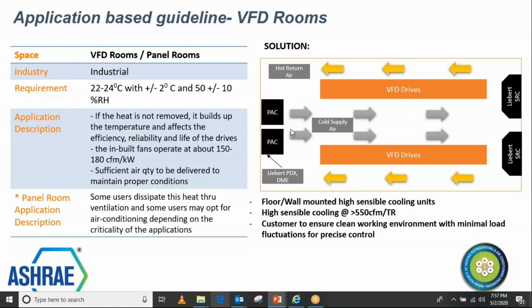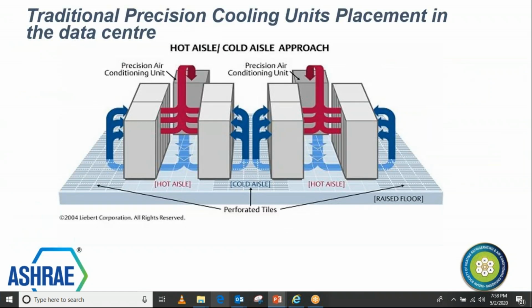This is just assumed here: the front discharge of the cold supply to the VFD drives, and the return coming from the side or from the top through the false ceiling. This unit can also be a ductable system. Suppose you have a plant room separately and you want a ductable system, then these kinds of systems can also be deployed. The overall objective here is that, similar to the other applications, this is also a very important application, and most of the applications are 24-hour applications, and the sensible heat ratio, airflow requirement and filtration requirement match precision AC, not a comfort air conditioning system. So this is also a precision AC application. I'm coming now to the data center side.